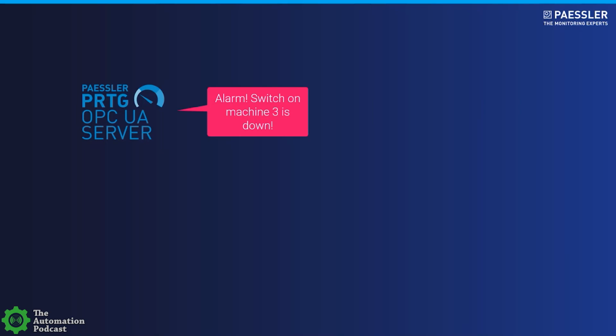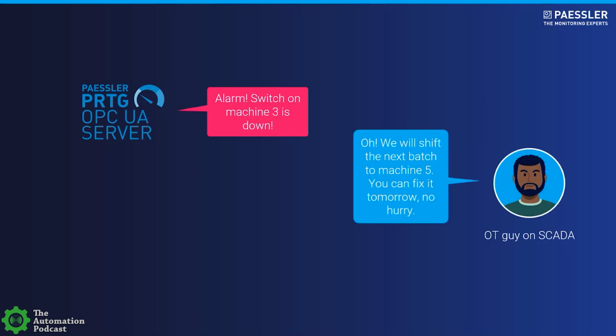And the benefit is here, and I have, again for the audio guys here, a small example. Assume it's on the weekend, probably Sunday, right? And the guy who is maintaining the network is not in the plant, so he's at home. And now the switch on machine 3 goes down. By integrating our alarms into the SCADA system, the engineer sitting in front of the SCADA will now get alarmed saying, oh, switch in machine 3 is down. But now, as he knows that this is the actual cause of the problem, he can decide, okay, we shift the next batch to machine 5, and because that works out currently, no problem.